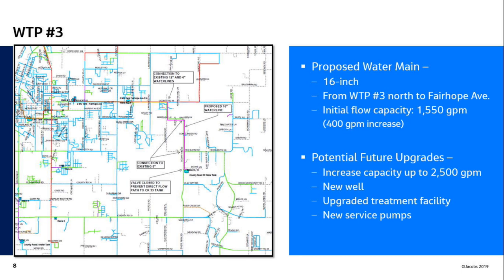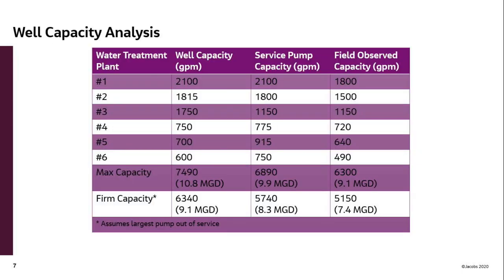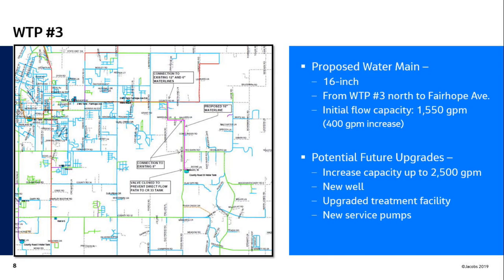One of the immediate fixes involves Well 3. Your well produces about 1,750 gallons per minute, but you can only pump about 1,150 into your system, mainly due to pressure concerns at the tank at Cambridge County Road 33. You have to valve it off during high demands. If we installed a 16-inch line from that well on County Road 33 to Fairhope Ave., tying into the 12 and 6-inch lines there, you would add about 400 gallons per minute — about half a million gallons per day — bringing firm capacity to about 7.8 to 7.9.